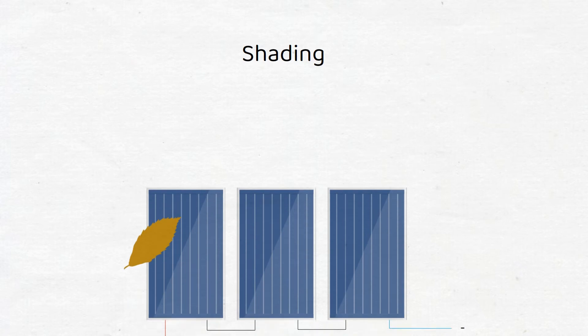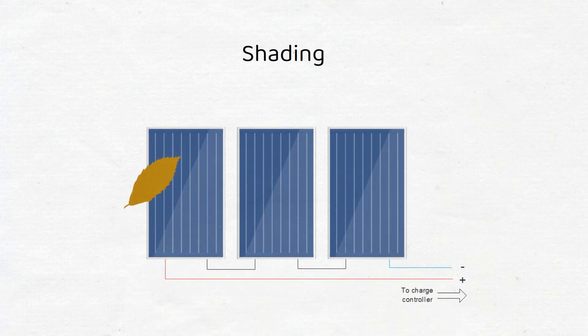Now, you might think that series is the best connection to make, because it will reduce your wiring cost. That is true if there is no shading. If, for example, there are 3 solar panels and one has shade, the whole string will suffer a reduced current output, because shade has impact on current, not voltage.